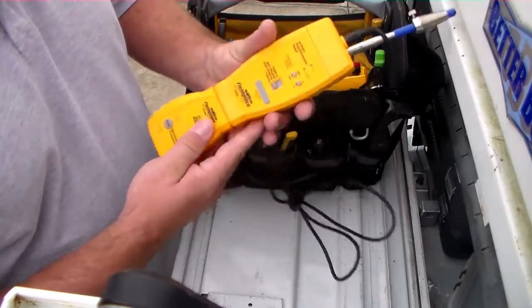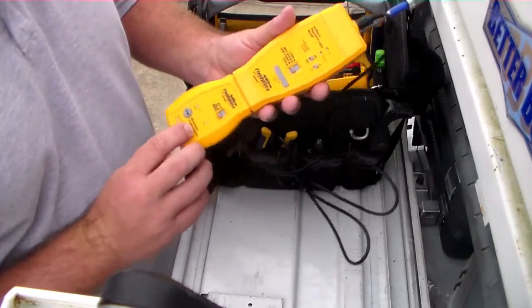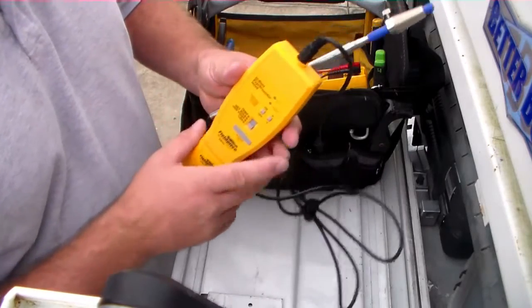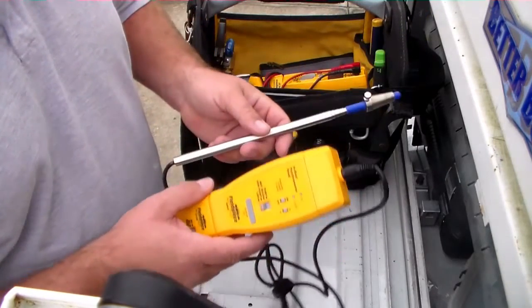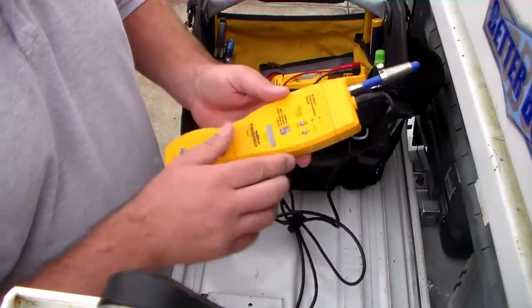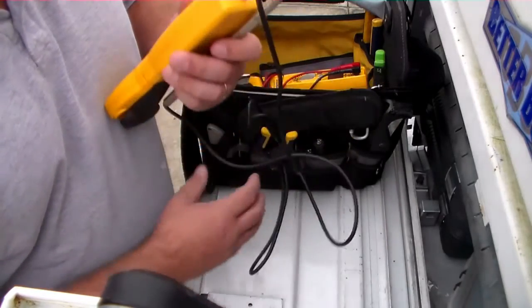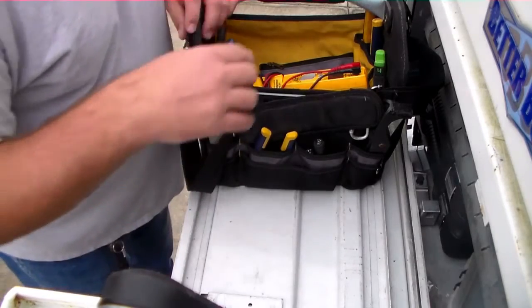This is a Fieldpiece wireless transmitter and the in-duct psychrometer head. If I want to get wet bulb, I can put it in the duct and broadcast it to my meter. It does temperature, wet bulb, dew point, or relative humidity, so I can get my target temperature split using our rule of thumb.